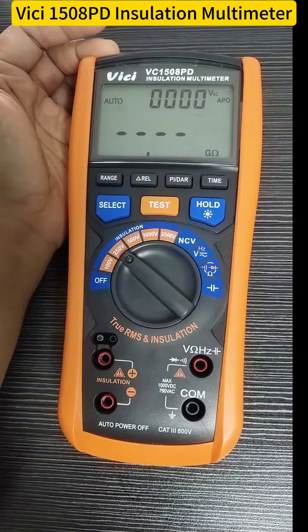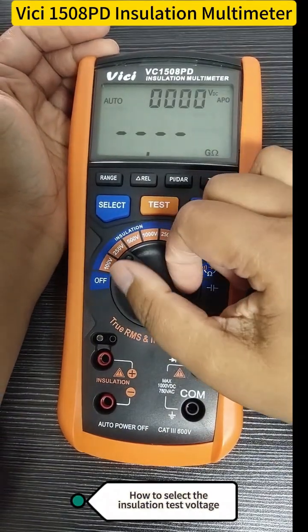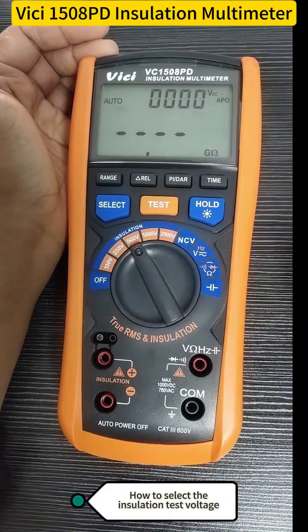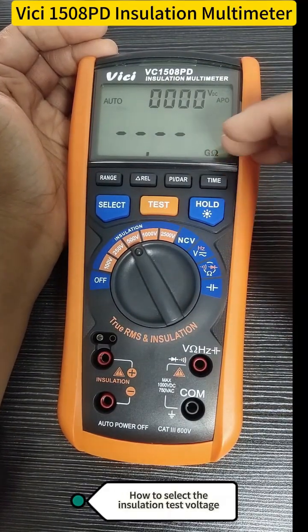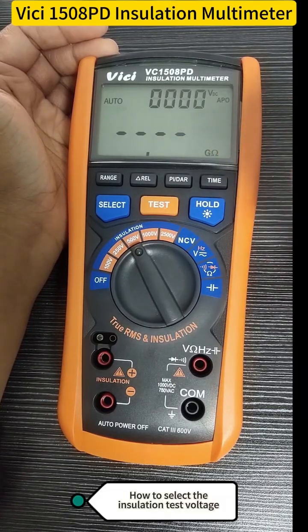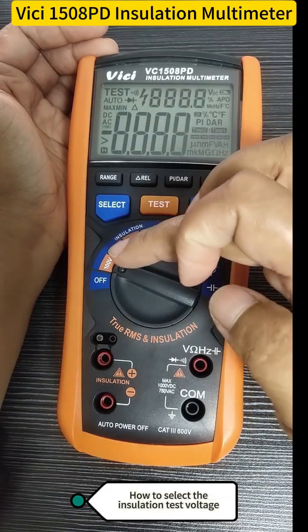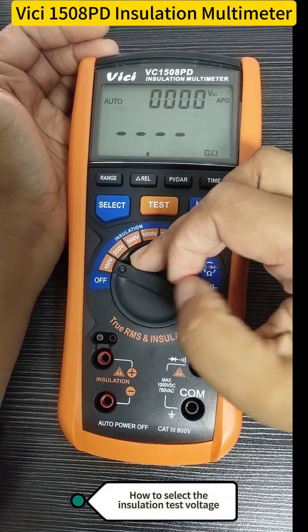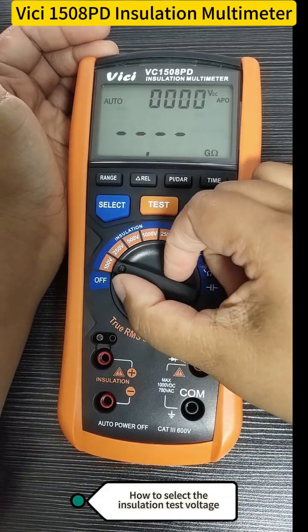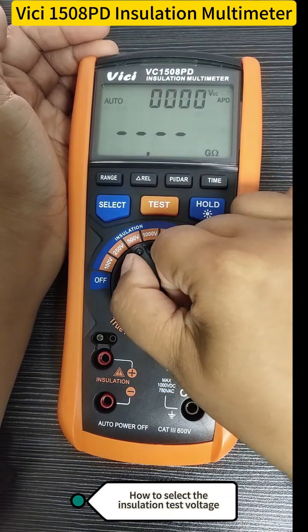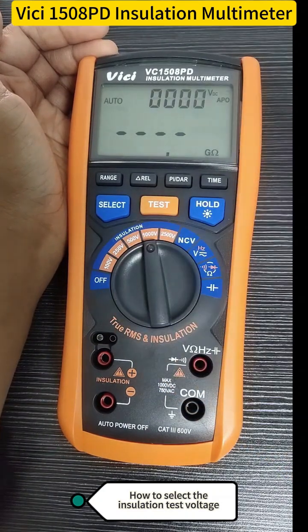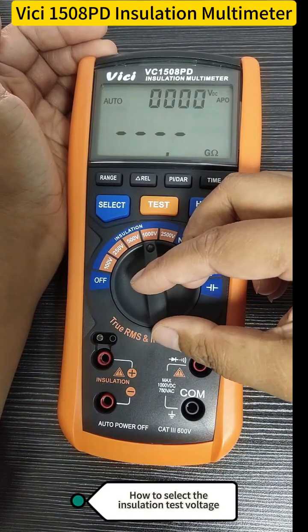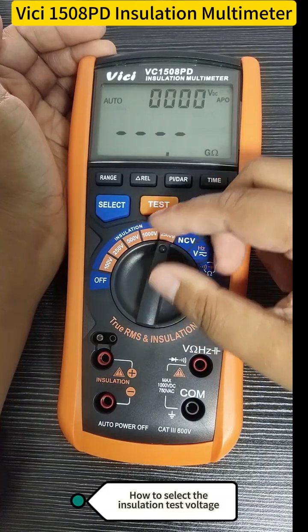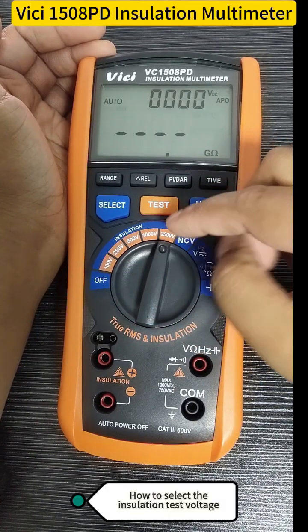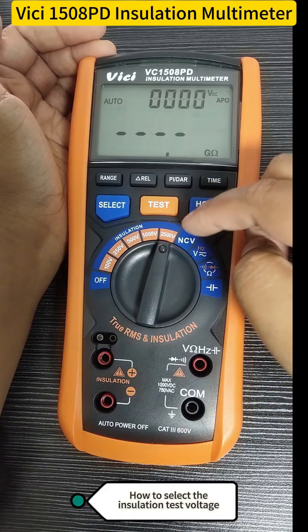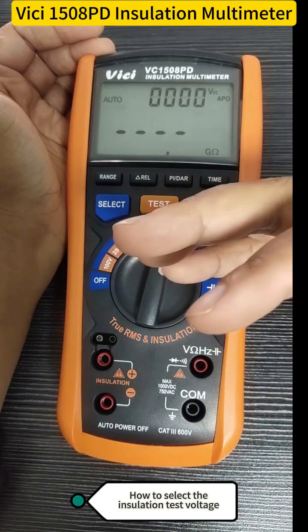Multimeter insulation. Okay, now let's get into the insulation testing tips. First of all, make sure the equipment is fully powered off before you start. We can pick the test voltage based on what we're checking. Use 100 and 250 volts for home appliances and low voltage gear. For 500 and 1000 volts, we can go to the motors, cables, and distribution boxes. For the highest gear of 2500 volts, use it strictly for large high voltage equipment. Don't just crank up the voltage randomly.